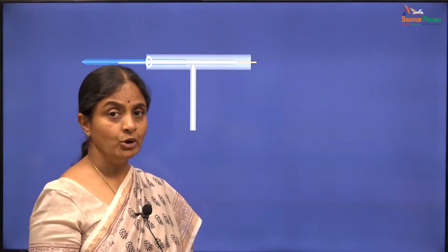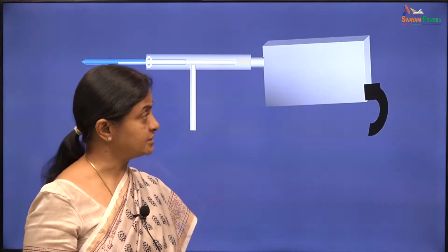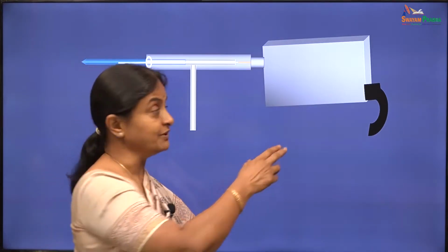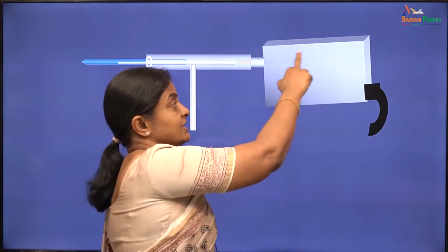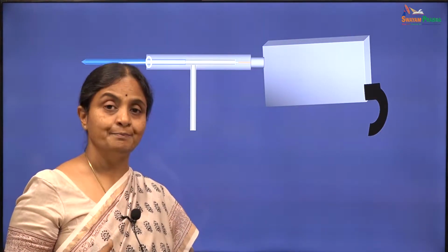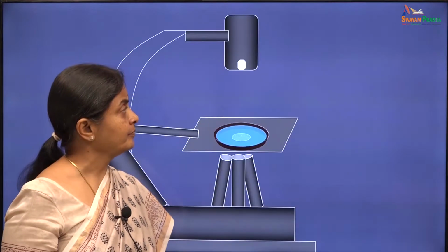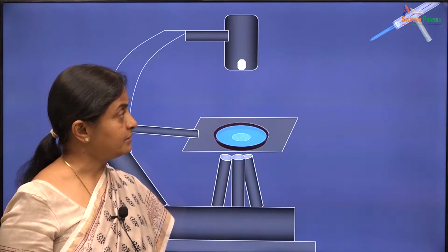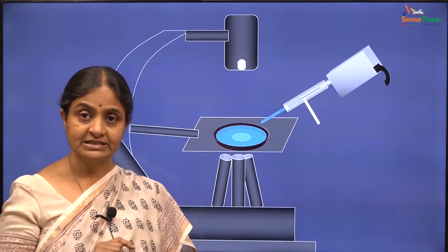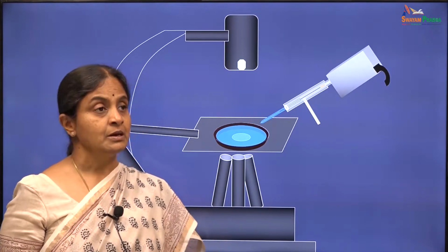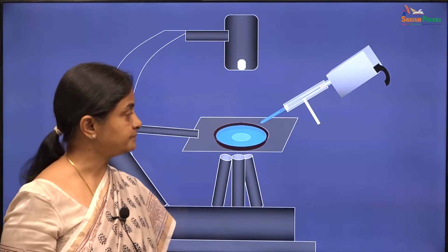This pipette holder assembly is then connected to what's called a preamplifier or head stage, in which exists the first level operational amplifier, which will measure the voltage. This whole assembly is then brought near the cell with the help of a micromanipulator, which can move in submicron dimensions under microscopic guidance.